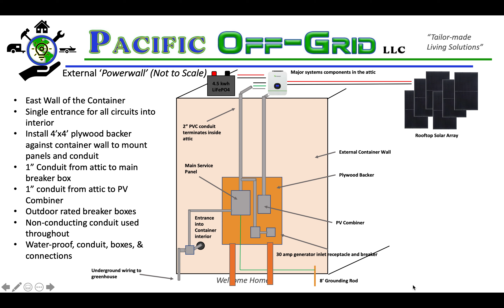So still looking at the east wall of the container, here we zoom in on the plywood backer onto which the main service electrical panel and the PV combiner are mounted. The current electrical architecture will provide the container and the greenhouse with 3,000 watts, or roughly 25 amps, of 120 volt power. We decided that 120 volt power was sufficient and that 240 volt was not required to meet the simple electrical needs of this project.